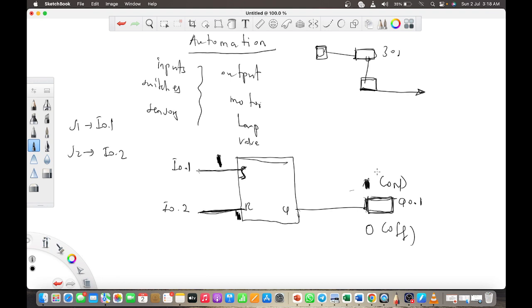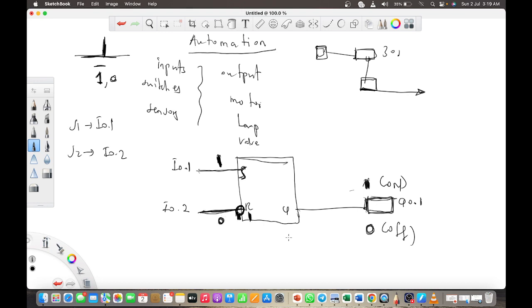For a stop switch you always connect it through a NOT gate before connecting it to the reset. Here's why: the stop switch in the circuit is normally closed, so it's allowing current through — it's at logic one. When I press the stop button it cuts the line, going to zero. So I NOT it to get a one at the reset, which gives me a zero at the output. Pressing stop gives zero, so NOT it to get one — that turns the output off.